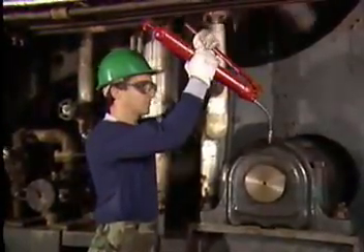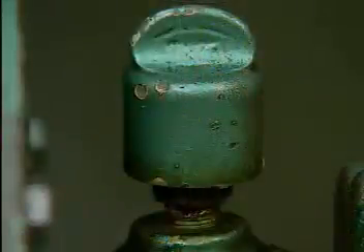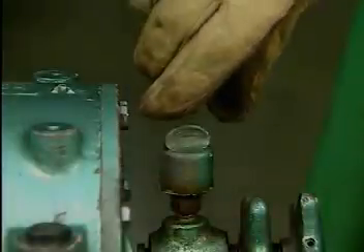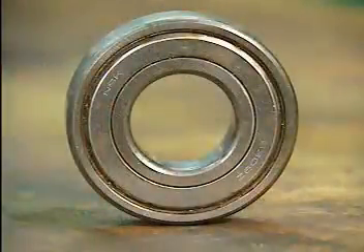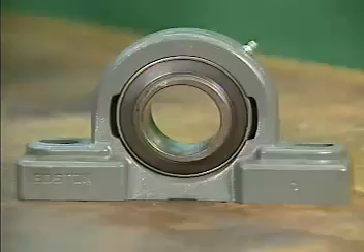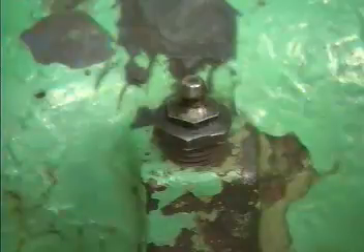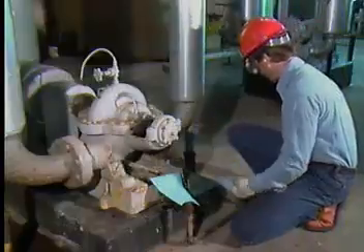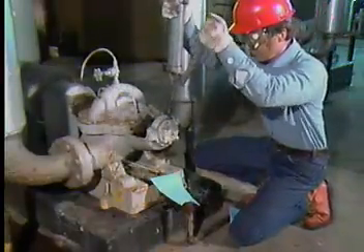They can grease the bearing with a grease gun, pack the bearing by hand, or use a grease cup. These methods are used only with bearings that are not sealed. Sealed bearings are permanently lubricated and they do not have to be greased. Many bearings that have to be greased are contained in housings that have grease fittings. A grease fitting is a small rounded projection on the housing that has a hole in it. To grease the bearing, a grease gun with a matching fitting is attached to the fitting on the housing.